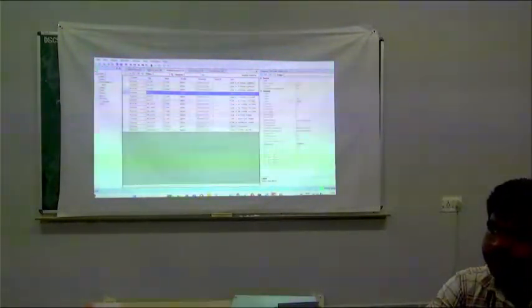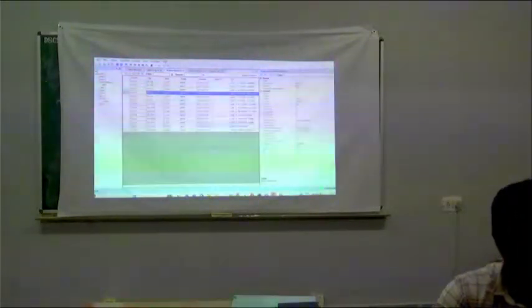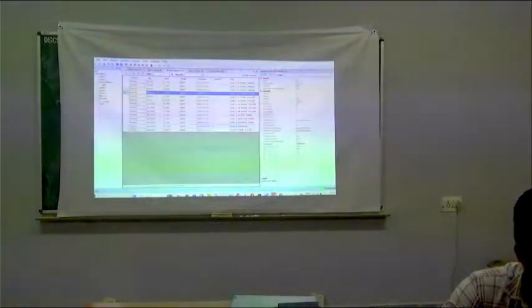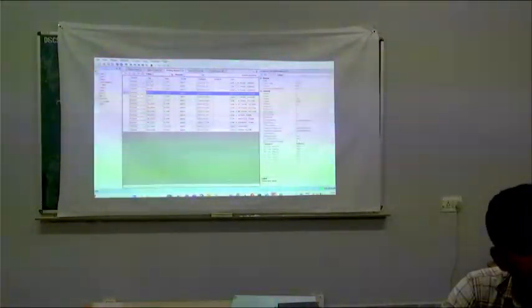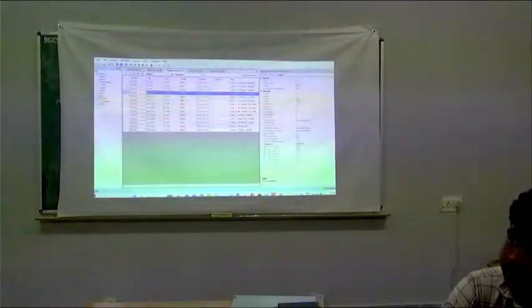This is what I am trying to tell you. What we can do is, this device communicates on 61850, whereas this one communicates on Modbus. There might be one more relay, say a protection relay which communicates on IEC 103. So for that also, I will refer the manual of that particular manufacturer. He would have specified the addresses at which that data is going to be sent. For that, I need to have an understanding of that protocol, how it works.